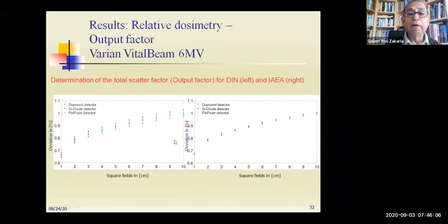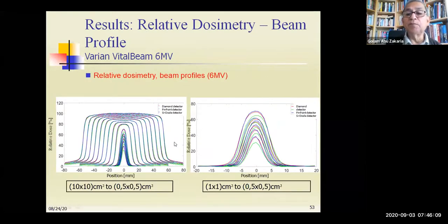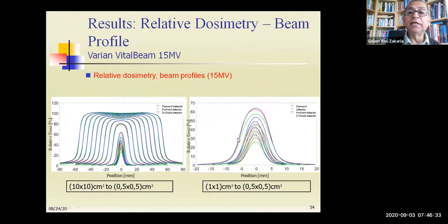And I will show you here relative measurements from the profile for 6 MeV. And you see for the larger fields, all 3 chambers show the same result, but for very small fields, you see some deviation. Yes, this is actually because of the volume effect of the pinpoint chamber. And again, it's 15 MeV. We can also measure here; the difference is a little bit more, because at 15 MeV the beam modulation is not as good as at a small energy like 6 MeV.